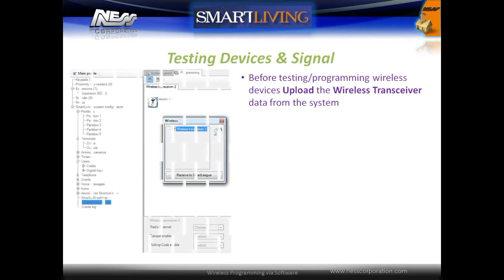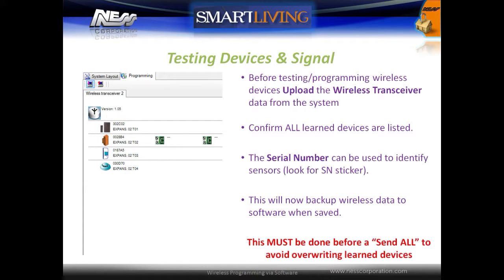Before testing or programming wireless devices, ensure that you upload the wireless transceiver data from the system. Select the wireless transceiver and then choose to upload. Confirm that all the learned devices are listed — the serial numbers can be used to identify sensors, and can be found on the serial number sticker on the device. This will back up the wireless data to the software when saved. It is important to ensure that all wireless devices are listed before doing a send all, to avoid overwriting any wireless data.